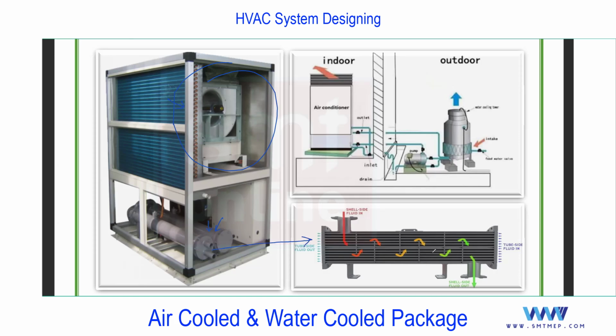Very simple. You see here the detailed view. If you talk about this line diagram, I can connect this pipe and this pipe here. I'll show you, but let me complete this shell and tube condenser first. You see, the outer one is called the shell. Inside you'll find the tubes, so we call it shell and tube. And here is the water in and this is the water out. H2O out and this is H2O in. Inside the shell you'll find the tubes, and inside the tube you'll find the refrigerant in. And here, using a pipe, the refrigerant out.